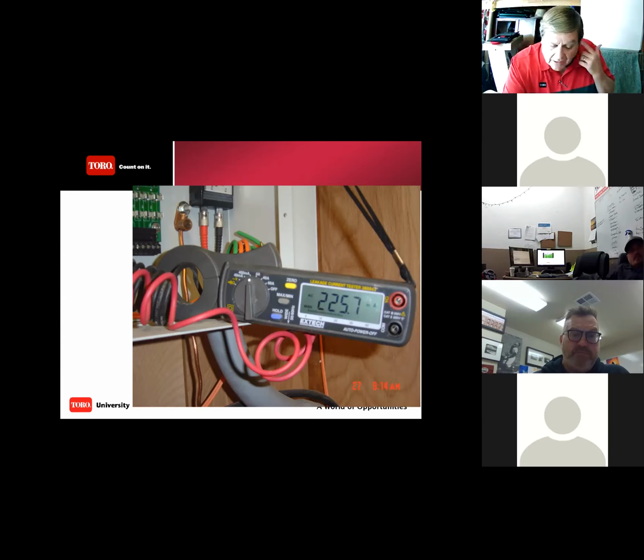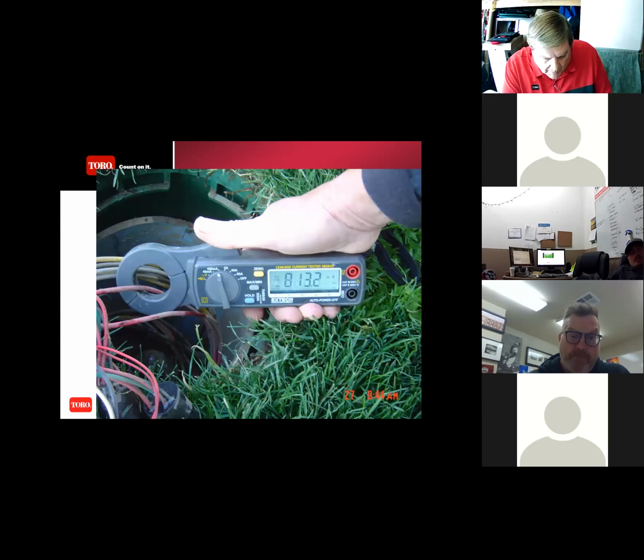Otherwise, if it's a high current draw like you see in the photograph here, 225.7 milliamps, this one's not blowing the fuse, but it's a high current draw, and I now have to follow the 2-wire path and go out in the field. From the clock to the first valve, oh my gosh, that's 813. That is huge. And in this situation, what this one turned out to be when I was doing it, it turned out to be a surge pill. If you look at the picture here, right here at the bottom of the screen, that is a surge pill.